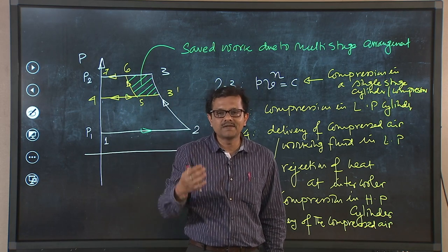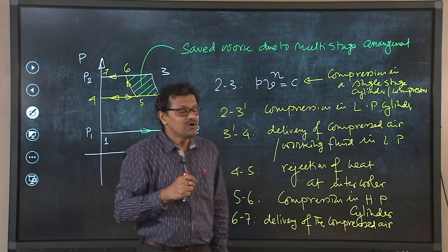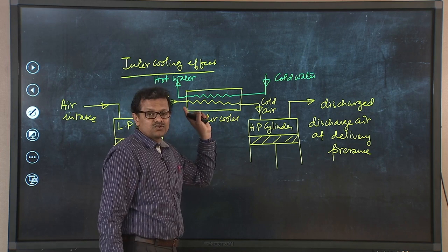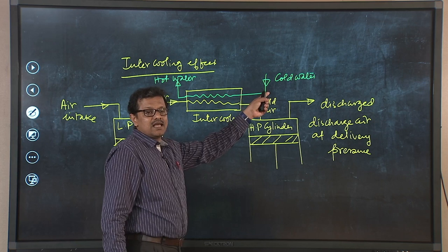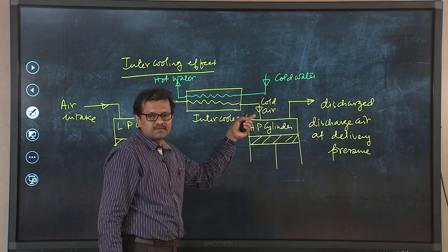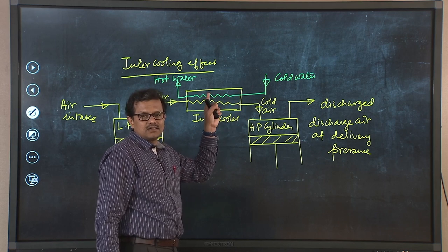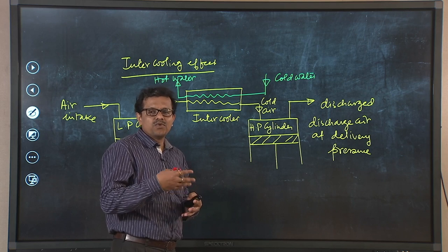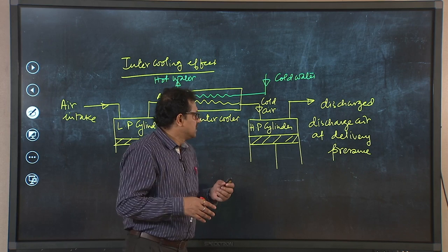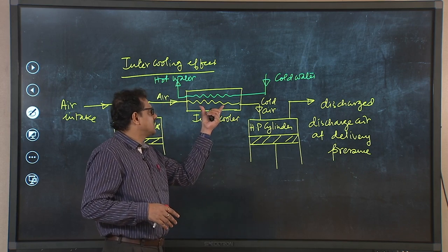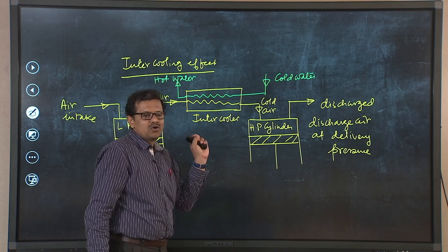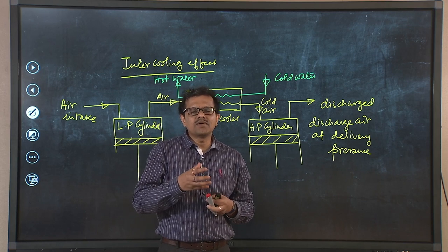But mind it, for this multi-staging arrangement we can save this much amount of work, that is true, that will certainly increase the cycle efficiency, but what is most important is that we need to have an important mechanical component, that is intercooler. So, what we need to do? We need to supply again one coolant that will take away certain amount of energy from the flowing gas or air or any other working fluid. To have such an arrangement, the system will be bulky, and for that both operational cost as well as maintenance cost would be there.